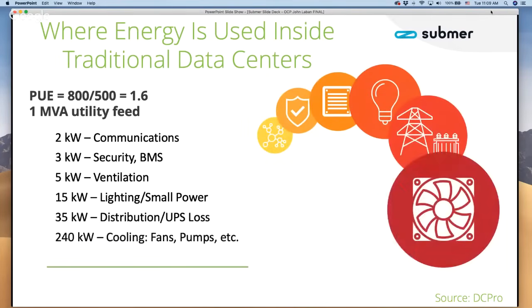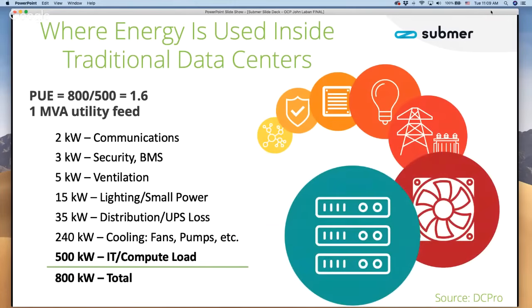Now, this is the energy in a typical enterprise data center, a tier 3. If it had a PUE of 1.6, this would be perhaps how the energy is distributed: 2 kilowatts on communications, 3 kilowatts security and ventilation, 15 kilowatts light and power, 35 kilowatts distribution and UPS losses, and then the big one — 240 kilowatts for cooling fans and pumps. Then the IT load comes in at 500.